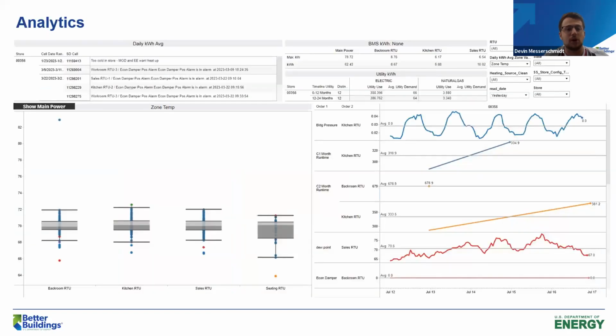This is our key auditing tool. We use this visualization to compare similar units across our portfolio against one another, based on energy use, zone temp, runtime, humidity, and other values. We use the box and whisker chart in the bottom left to find outliers. There are also different colored dots depending on what stage of the process they're in. We can sort sites based on location such as state, configuration type, which is something we group them into, the heating source, electric or natural gas, and other factors we deem important, such as square footage or tonnage on the roof.